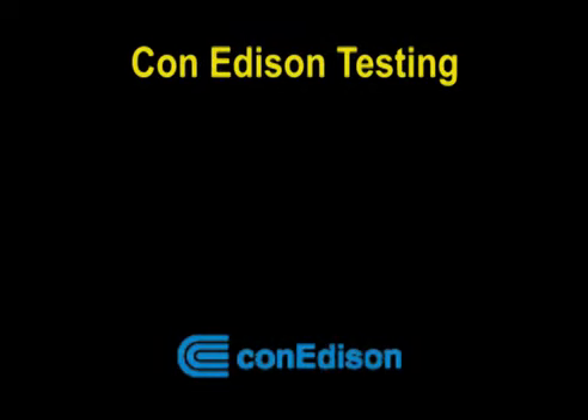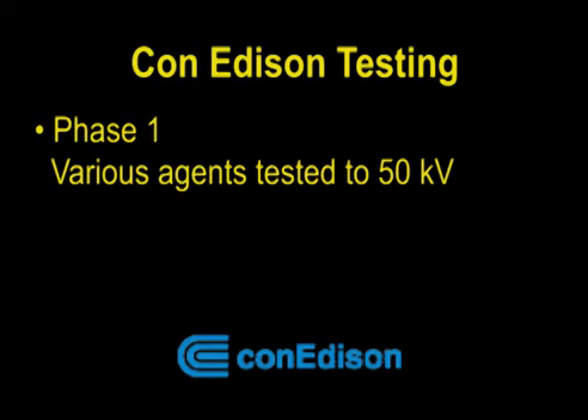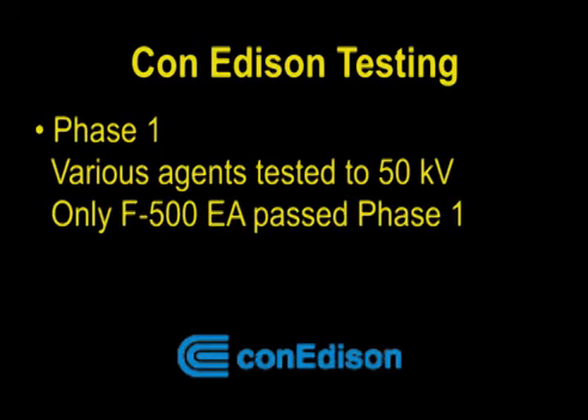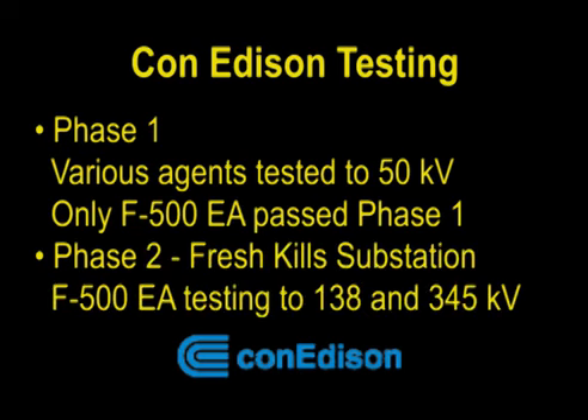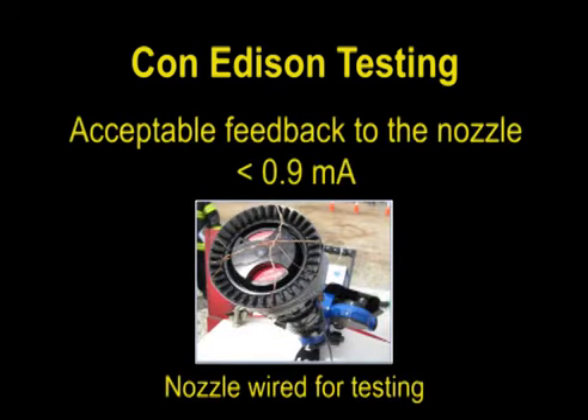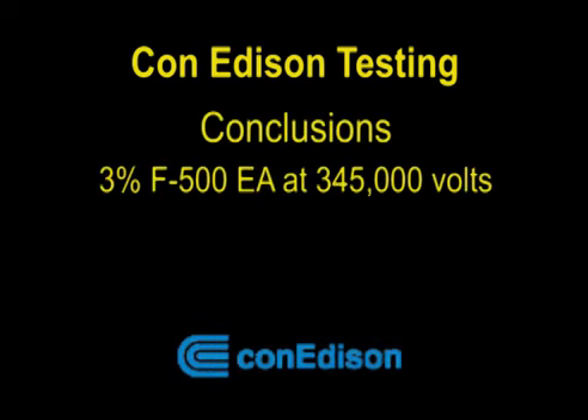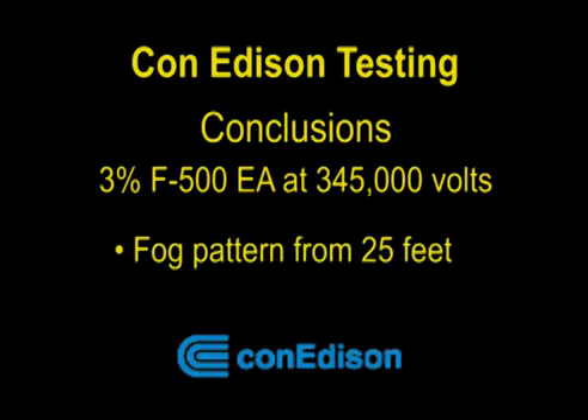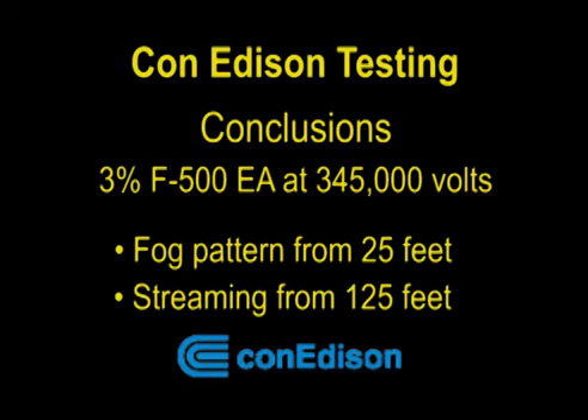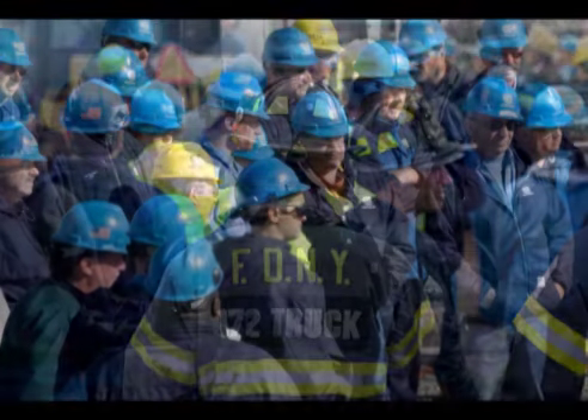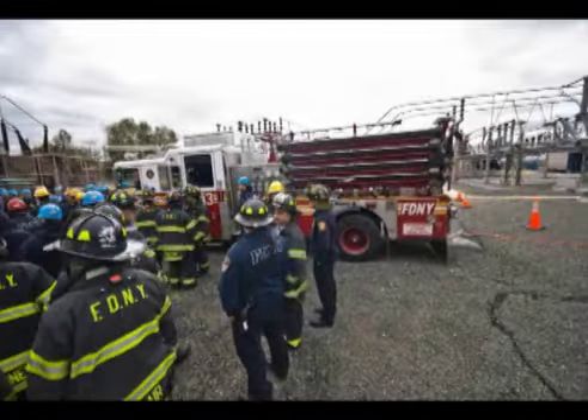After this incident, ConEdison began testing various fire suppression agents. Preliminary tests at 50,000 volts showed only one agent had acceptable electrical feedback to the nozzle, F500 encapsulator agent. In October 2010, live field testing began at the Fresh Kills substation on 138,000 volts and 345,000 volts. To be imperceptible to humans, the electrical feedback to the nozzle had to be below 0.9 milliamps. Their findings showed 3% F500EA could be applied to 345,000 volts from 25 feet with a fog pattern or 125 feet with a stream. As a result of the ConEdison testing, F500 encapsulator agent is now recommended for transformer fires.